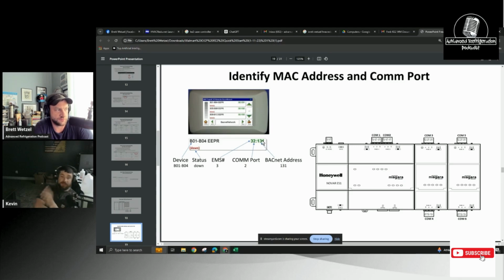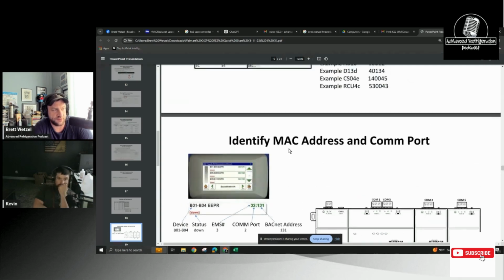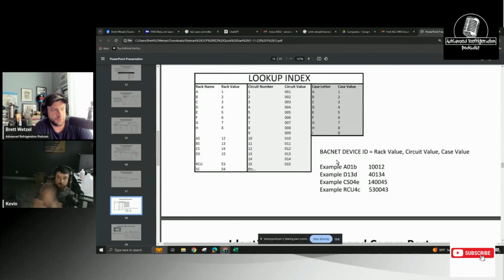These controllers have BACnet addresses and BACnet instance IDs, and they're different. The instance ID is how it's written out. If both aren't properly entered, the devices will not communicate. Some controllers don't use BACnet addresses, some only use instance IDs, and some use both. This one has both: the BACnet address here, and also the instance ID.